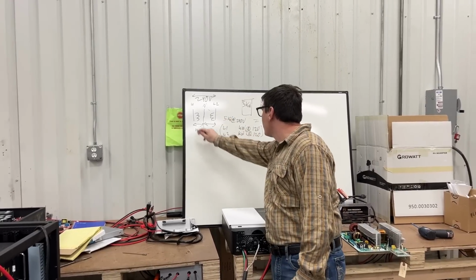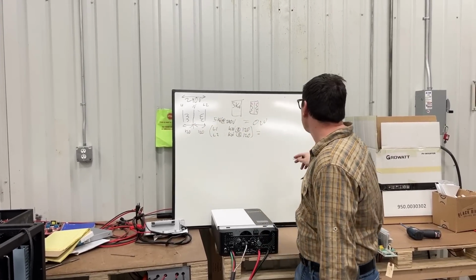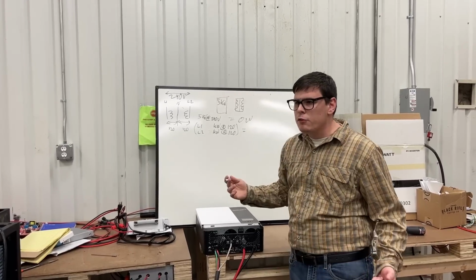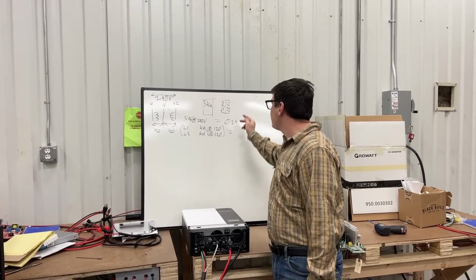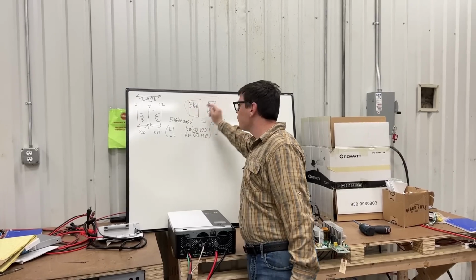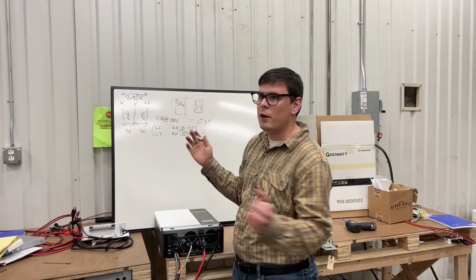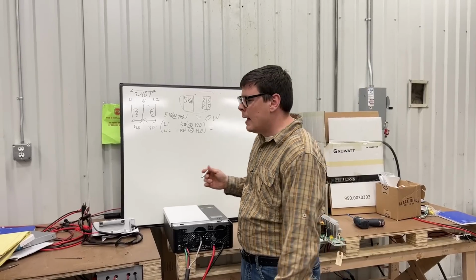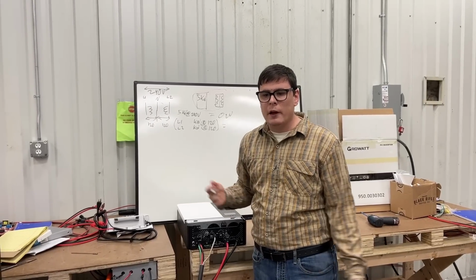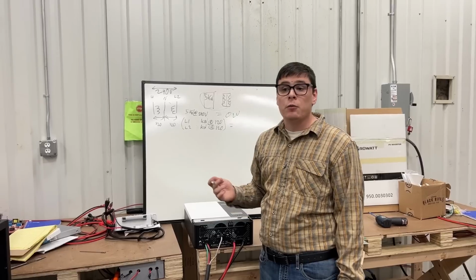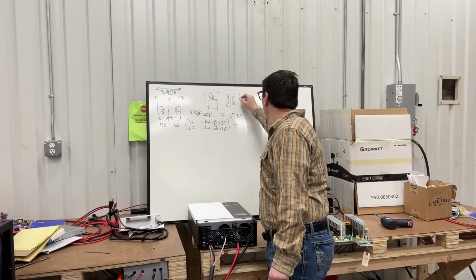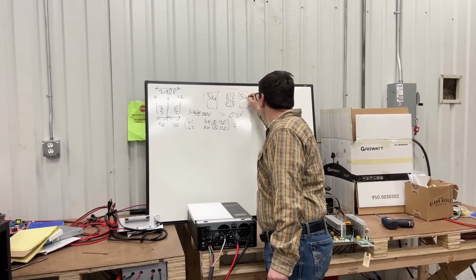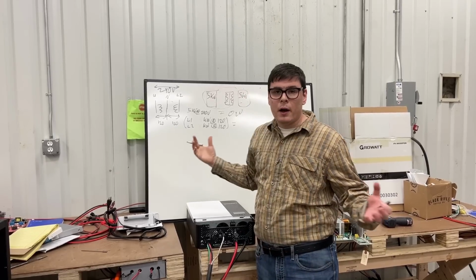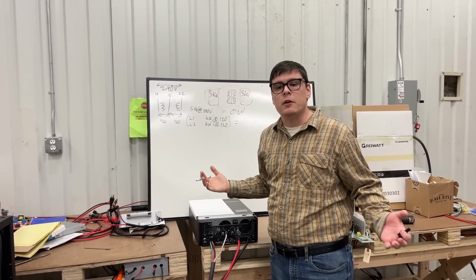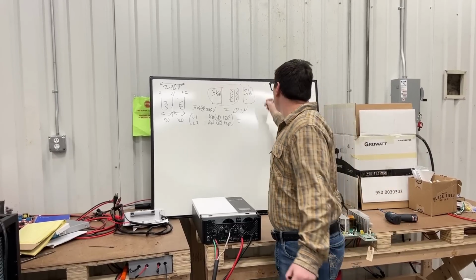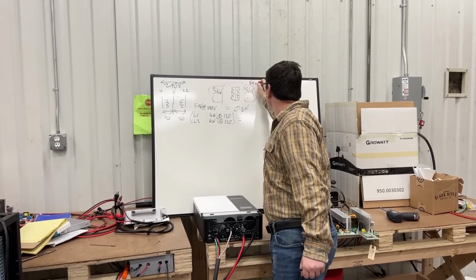And so basically, just understanding the value behind the 5000ES and the 240 volt inverter modules is that if you're an off-gridder and you buy a 5 kilowatt and a transformer, and it's more than enough to cover your 120 volt loads, and you say, you know what, we'd like to put a dryer in. Well, guess what? You only have to buy a 5 kW. You don't have to buy anything else. We don't make you buy something you don't need, because that is $900.